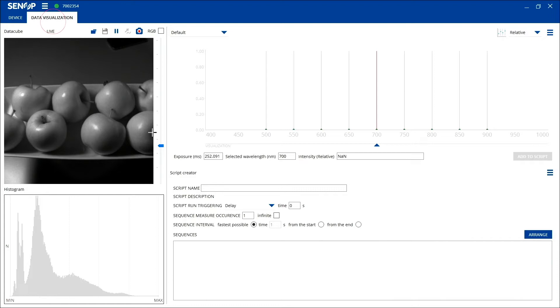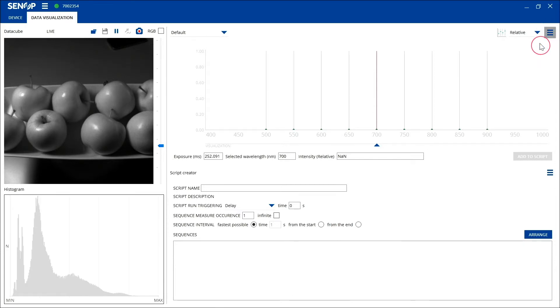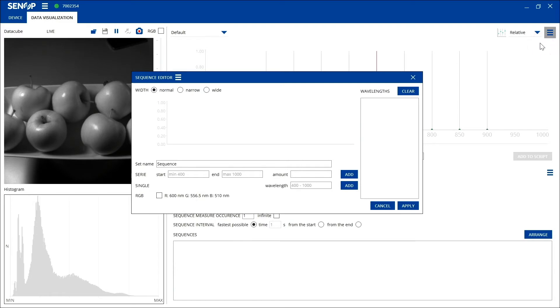When you want to take a specific image using the HSC-2, start from creating a sequence. In the sequence you choose the wavelengths and exposure time for your imaging purposes. This is done by clicking the menu in the upper right corner and selecting new. Now the software opens a new window where you can create your sequence.